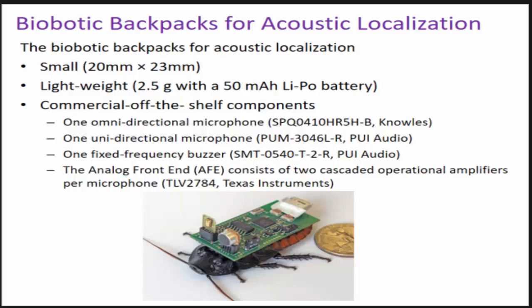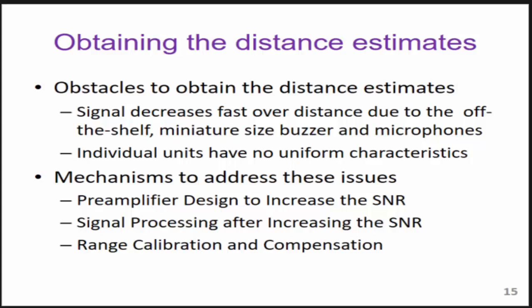So what embedded system programming is necessary to go into it? Before then, let me tell you about the limitations. First of all, the signal decreases really fast due to off-the-shelf components and miniature size. Secondly, individual units don't have uniform characteristics. The solution to all of those is in these three bullet points: a preamplifier design to increase the SNR, some signal processing, and range calibration to compensate for microcontroller time delay.